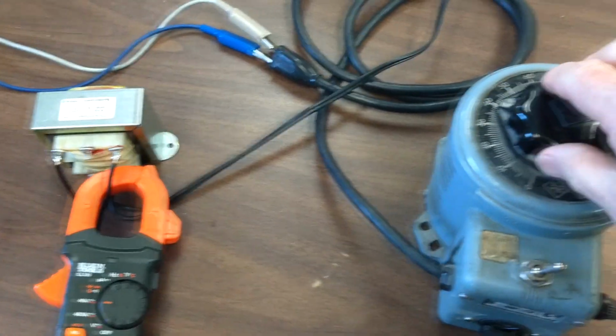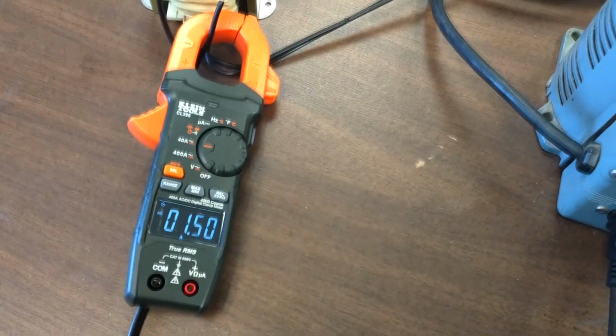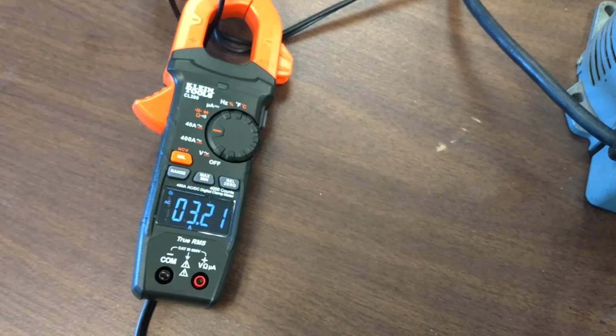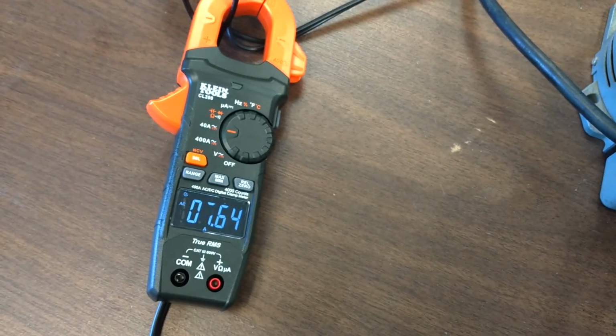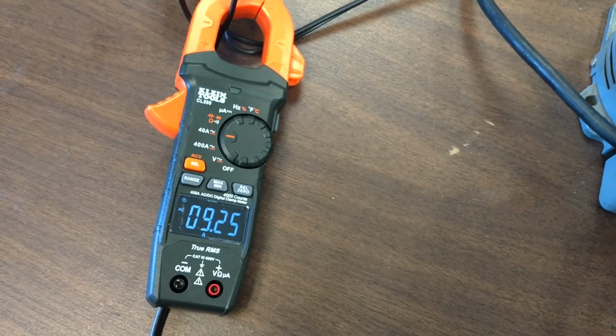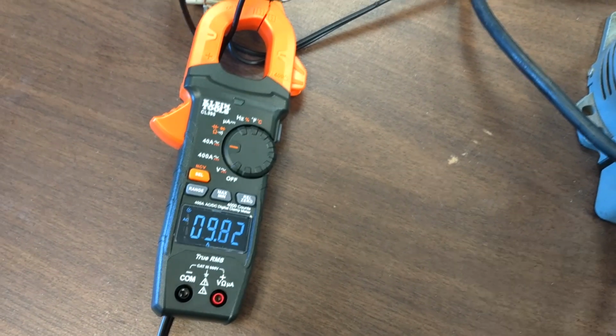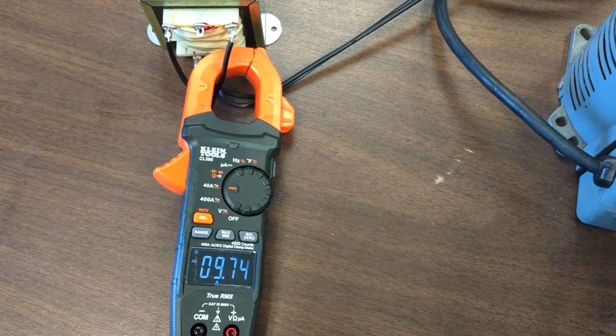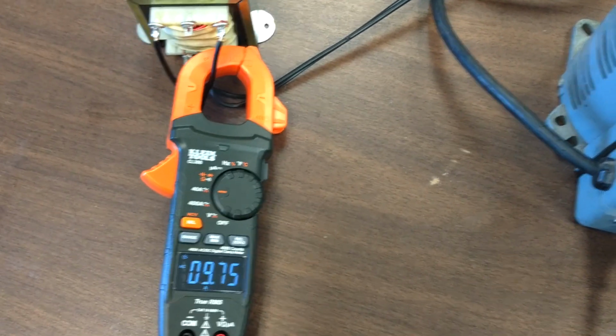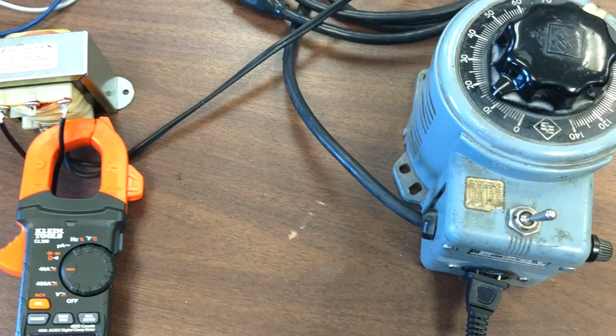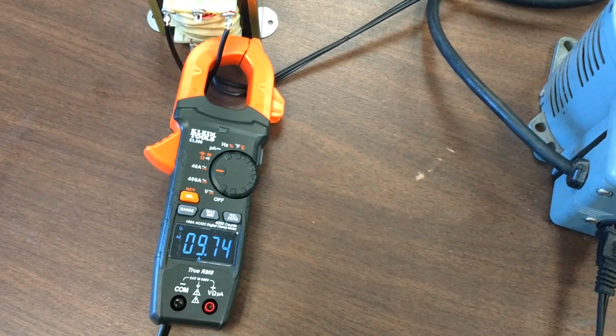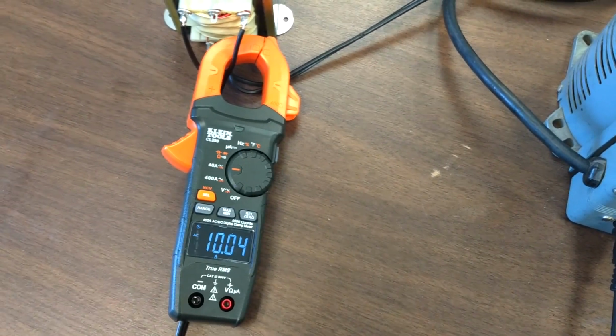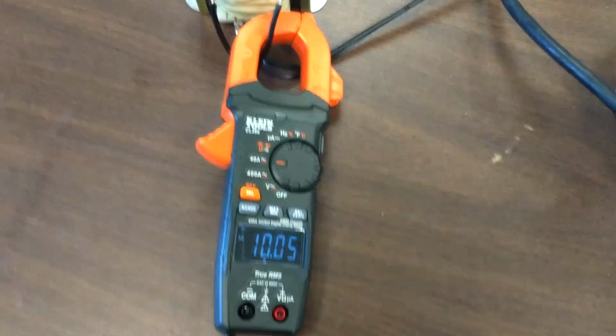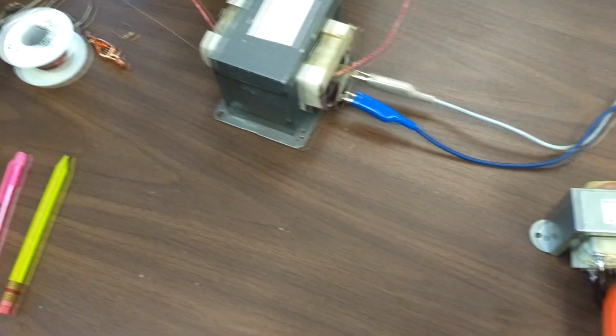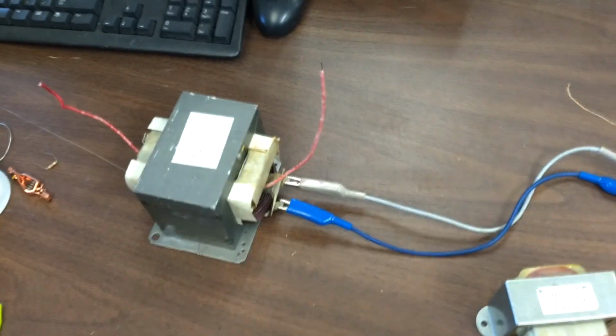So as I bring the turns ratio down, we see the current going up. And there's approximately 10 amps. It's difficult to get exactly because of the voltage step between just one turn in the variable transformer. But basically, there's a 10 amp load with essentially no power dissipation.